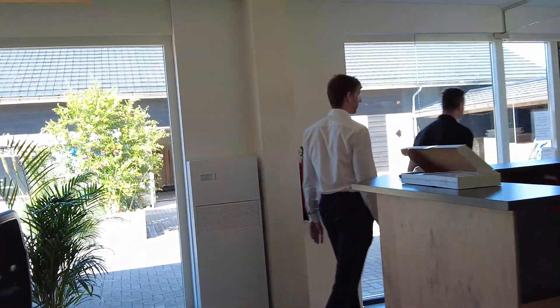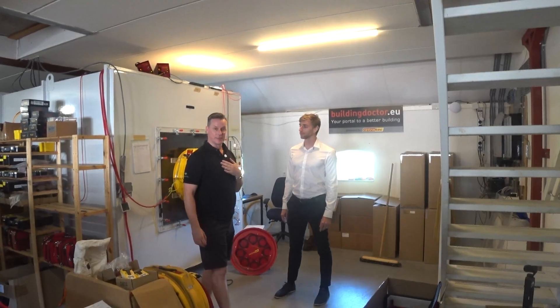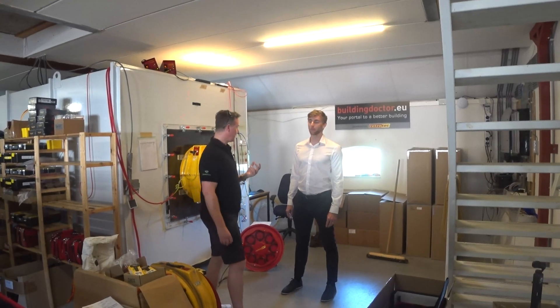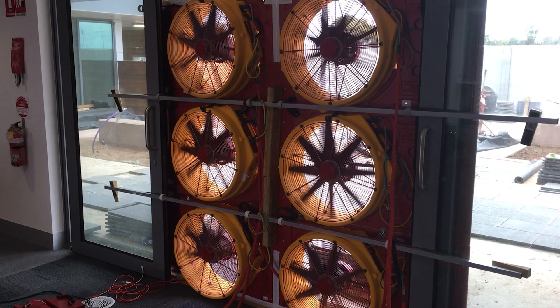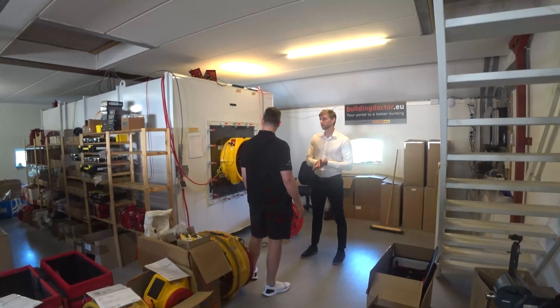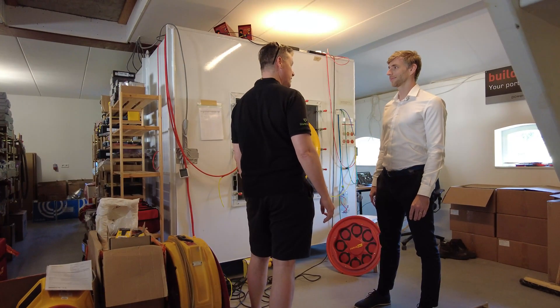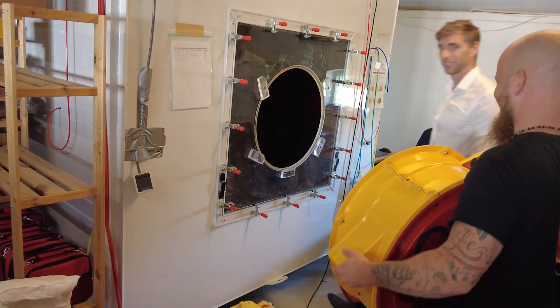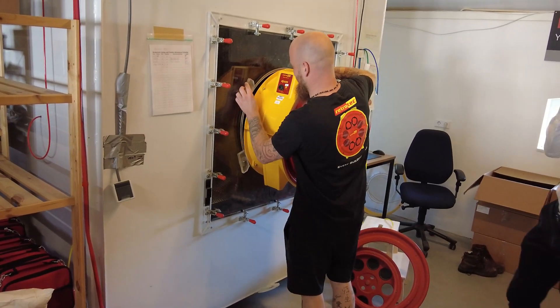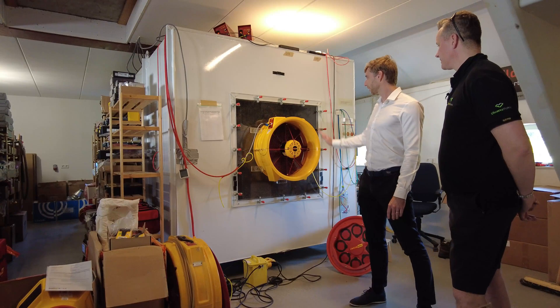We're going to go through the calibration of our Retrotec fans. Retrotec fans are very close to our heart at Efficiency Matrix — these are predominantly the fans we use to test the biggest buildings we get access to in Australia. Rob is going to take us through the process they go through in this rig that you guys have engineered. This rig here is our calibration unit — we've actually got two more smaller ones in different sizes. This is our biggest one, and this is what we use to calibrate the fans.